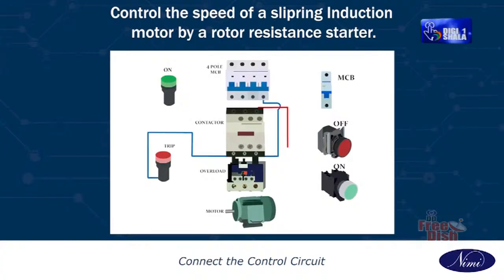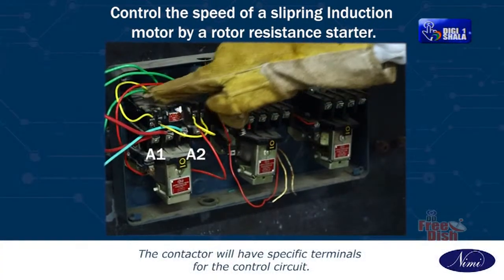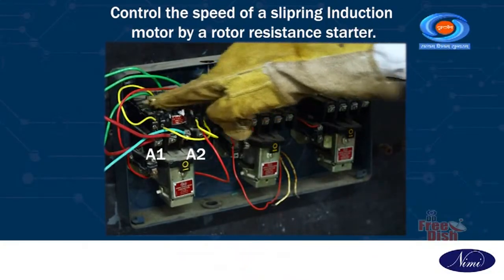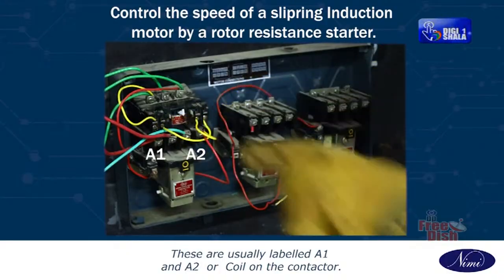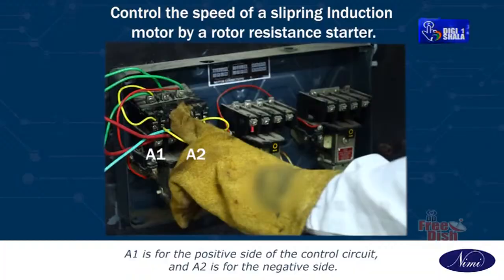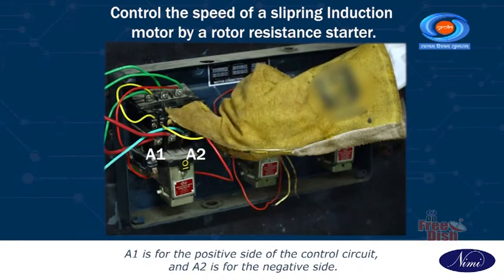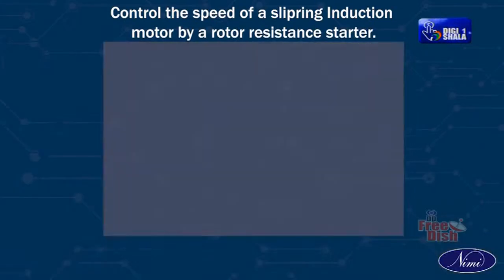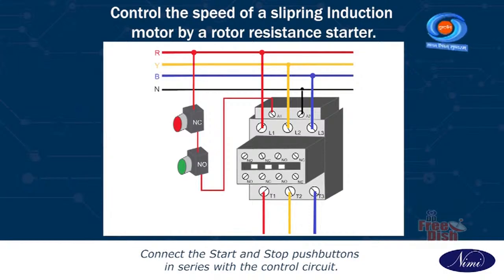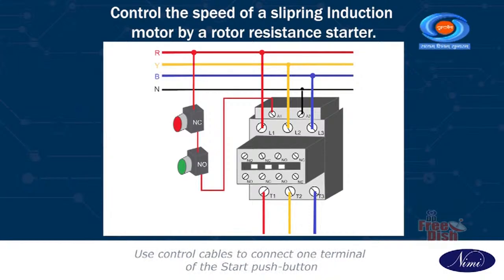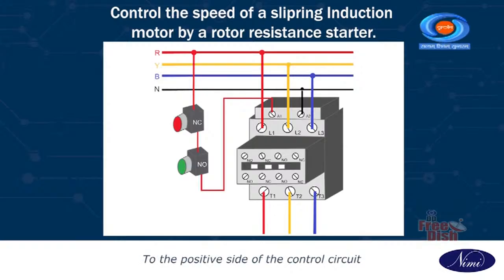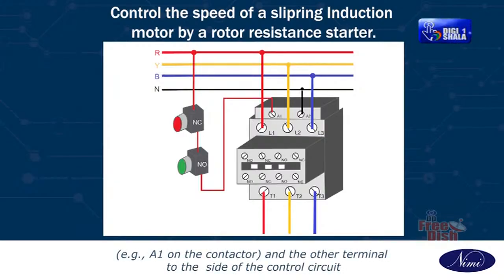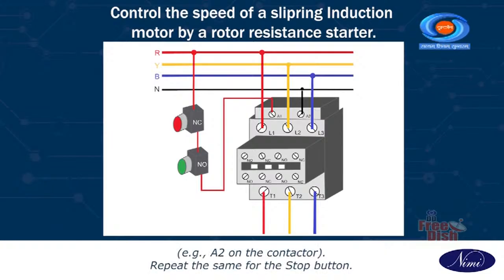Connect the control circuit. The contactor will have specific terminals for the control circuit. These are usually labeled A1 and A2 or coil on the contactor. A1 is for the positive side of the control circuit and A2 is for the negative side. Connect the start and stop push buttons in series with the control circuit. Use control cables to connect one terminal of the start push button to the positive side of the control circuit, example A1 on the contactor, and the other terminal to the negative side of the control circuit, example A2 on the contactor. Repeat the same for the stop button.